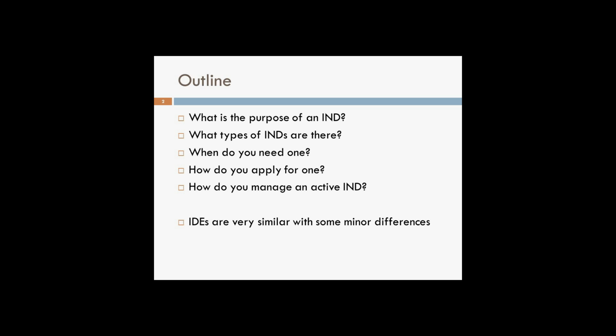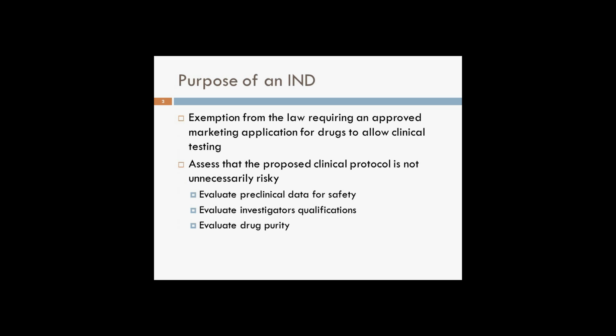IDEs, investigational device exemptions, are very similar to INDs. There are some minor differences, but we'll really focus on INDs today because they have the most structure to them. The FDA has really strict requirements for what needs to be in an IND application, and there are a lot of forms associated with them. We were surprised when we submitted our first IDE to the FDA. We asked, where are the forms? And they said, just send us what you think we need to know. So there was a different attitude, but we got it approved. Sticking things in brains of people, apparently they're okay with that. But today we'll focus on INDs.